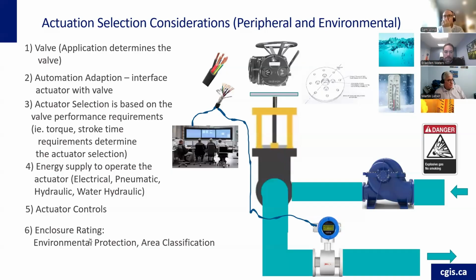Last but not least, environmental protection. There are applications where actuators get drowned. They're down in manholes or whatever, and twice a year they get covered in water. So it's important that we look at an actuator that has an IP68 rating, or an IP rating that is suitable for that. And it could be a very corrosive environment where you need additional coatings on the valve, on the actuator.